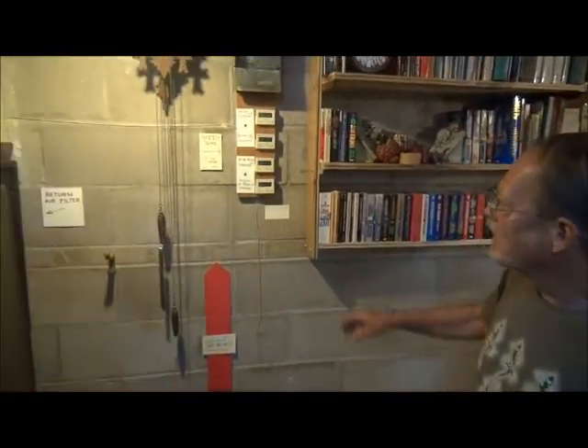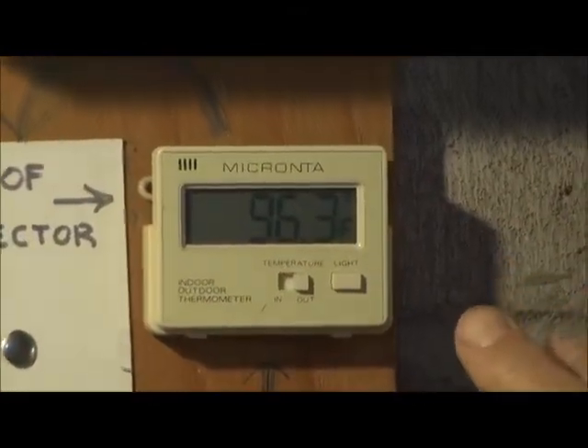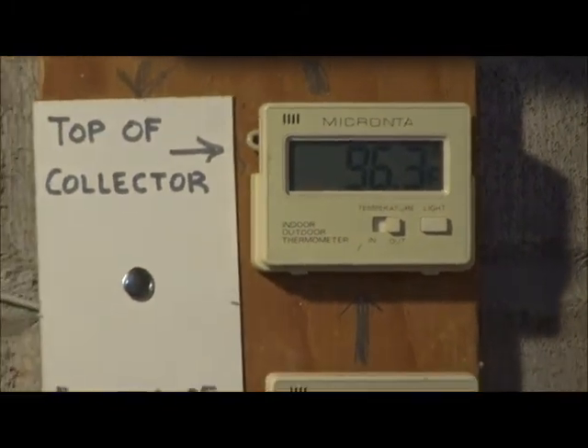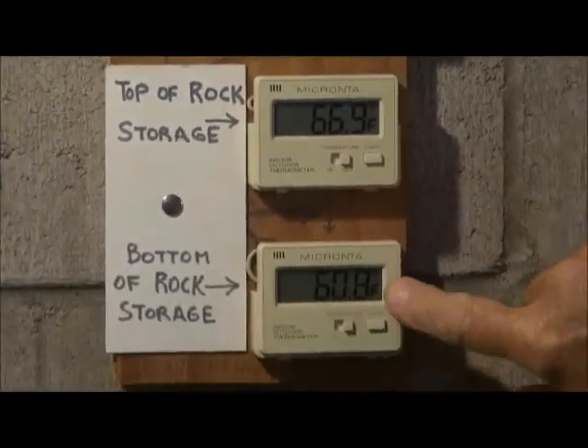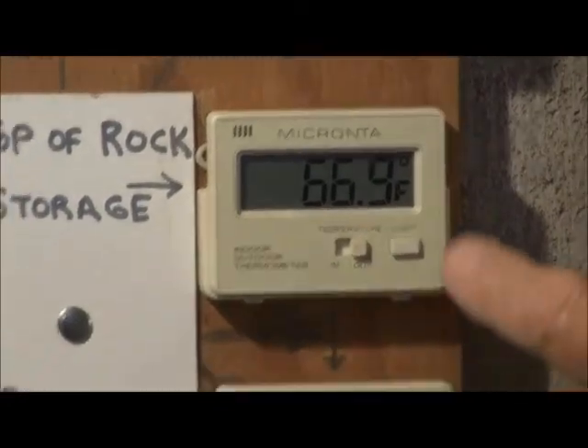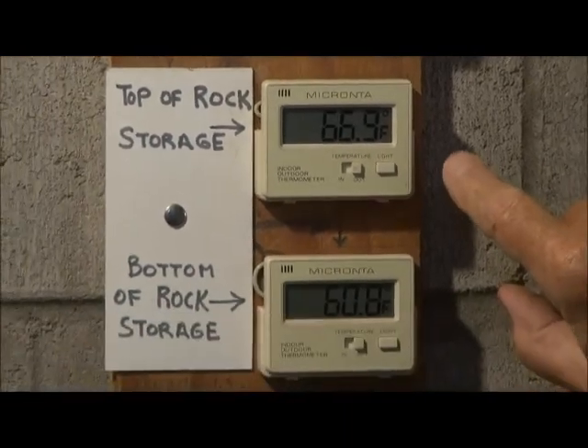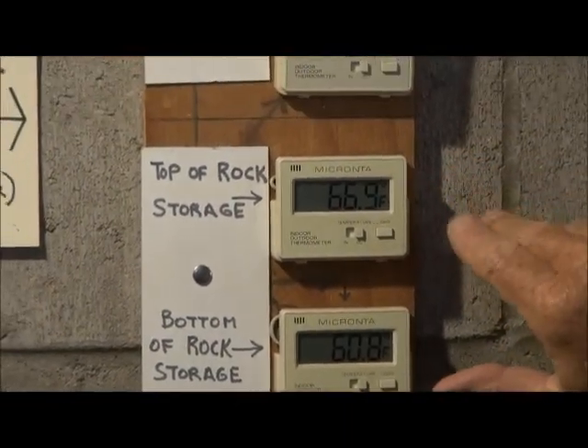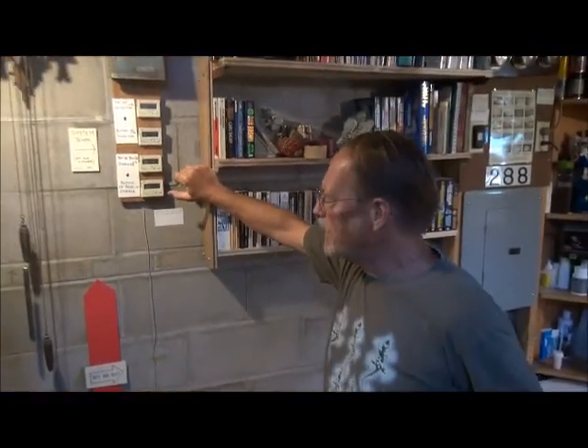In the basement, temperature gauges show the top and bottom of the collector. The system is turned off right now, but air is convecting out at 96°F at the top. Rock storage is coasting at 61°F at the bottom and 67°F at the top. In winter when heated up, it'll reach maybe 105°F at the top of the rocks. It takes three or four days to charge up, storing enough heat for two or three days. The system provides about 60 to 70 percent of their winter heat; the rest is electric baseboard backup.